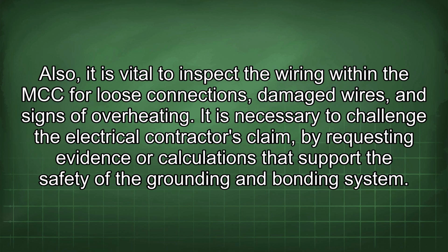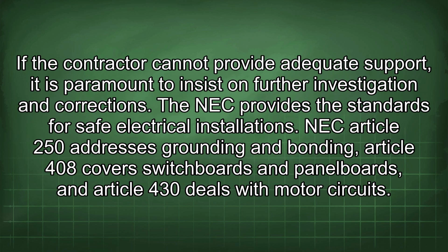It is necessary to challenge the electrical contractor's claim by requesting evidence or calculations that support the safety of the grounding and bonding system. If the contractor cannot provide adequate support, it is paramount to insist on further investigation and corrections. The NEC provides the standards for safe electrical installations.